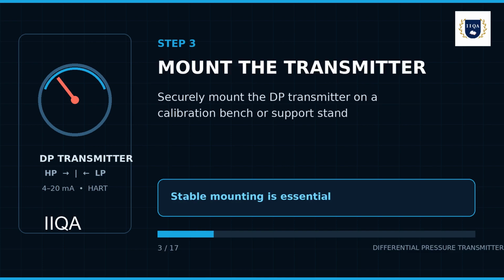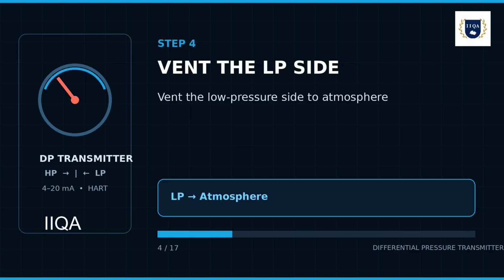3. Securely mount the transmitter on a suitable calibration bench or support stand. 4. Vent the low pressure, LP, side of the transmitter to atmosphere. 5.